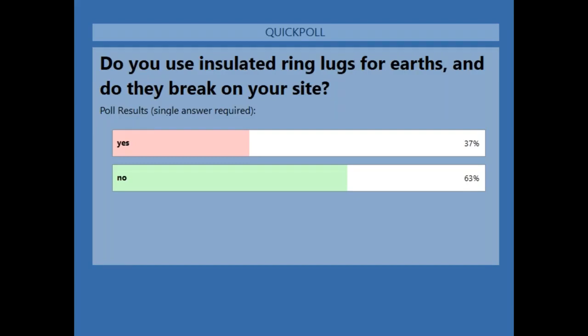So, do you use insulated ring lugs? Bit of a contentious poll. I didn't give it enough options, but I would hope that the no is 63% no, as in we don't use them. But this 37% that say they do use them, they do realize they break. To give people without the field experience, or let's say on an existing asset, they break all the time. Why? They're a commercial grade product. They're used because they're cheap.